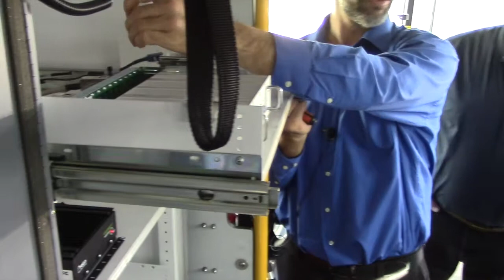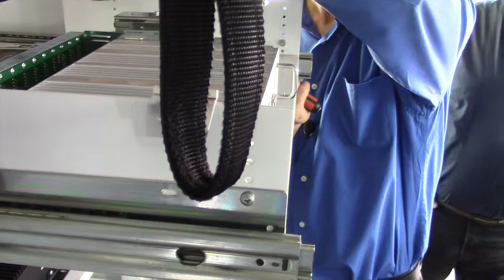I just pull this, and what you want to do is on the top there's a snap ring. You push on that, and it'll get you to the D-sub. You're going to grab both ends of the D-sub, release that, unscrew it from the base, put it back in. All the D-subs will have a high side and a low side. This is sub D9, so you're going to have 5 up top, 4 on the bottom. Just line it back up.